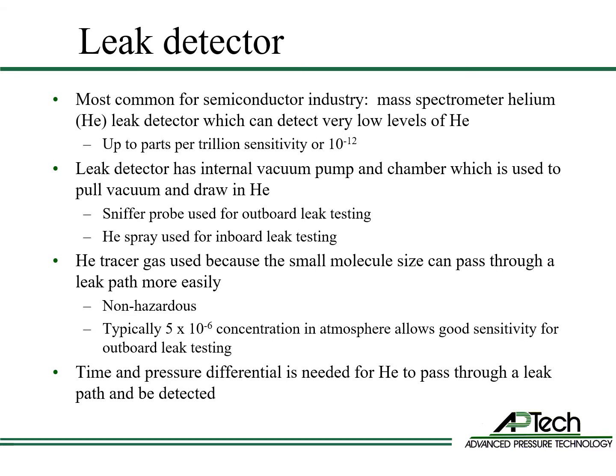In the semiconductor industry, a helium mass spectrometer is the most common type of leak detector. It uses vacuum to detect leaks. The mass spectrometer can detect very low levels of helium, some down to parts per trillion, or 1×10⁻¹² concentration of helium. Its internal vacuum pump and vacuum chamber pull vacuum and draw in helium. Helium is used as the tracer gas because its small molecule size passes through leak paths more easily than larger molecules. Helium is also non-hazardous and has naturally low concentrations in the atmosphere, typically about 5×10⁻⁶. This allows for good sensitivity when leak testing for an external leak into atmosphere. Time and pressure differential are needed for the small volumes of helium to pass through a leak path and be detected.